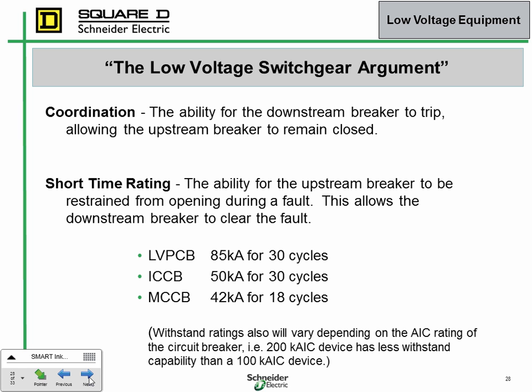Right? And if there's a fault that occurs there, the main breaker won't see that fault. It won't react. It's a device on the other side of that transformer, on the medium voltage side, that's got to take that fault out. And that's why, if it's a service entrance, you're automatically pretty much dangerous. Now, by applying ARMS switches to the branch breakers in that gear, you're reducing the arc flash in all the downstream panels that it's feeding, but you're still dangerous over here. And that's with switchboards.